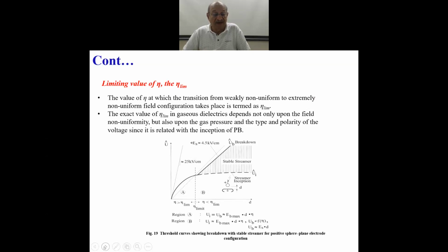So the value of eta, I'll just read it out. The value of eta at which the transition from weakly non-uniform to extremely non-uniform field configuration takes place is termed as eta limit. We'll devote a few minutes to learn about eta limit. The exact value of eta limit in gaseous dielectrics depends not only upon the field non-uniformity, but also upon the gas pressure.